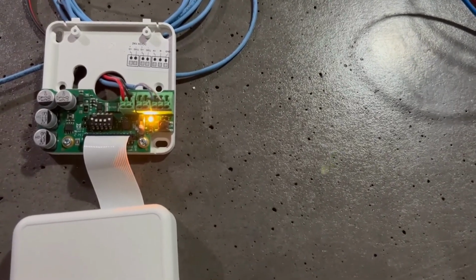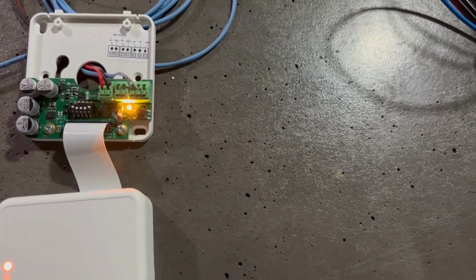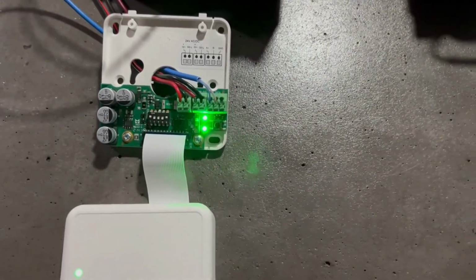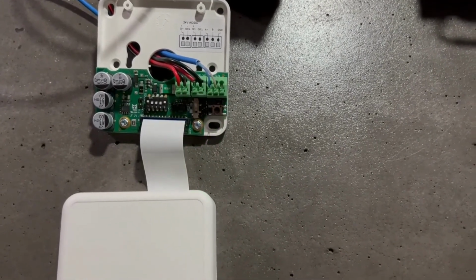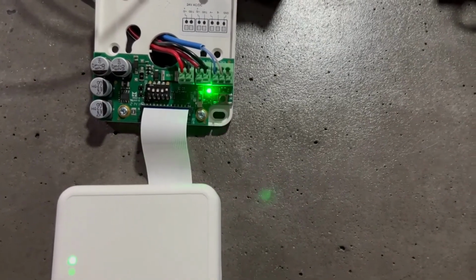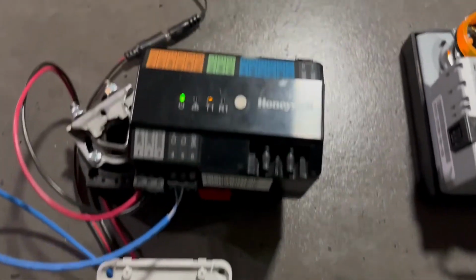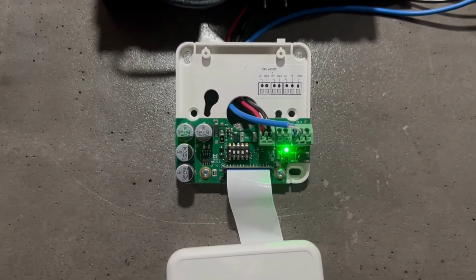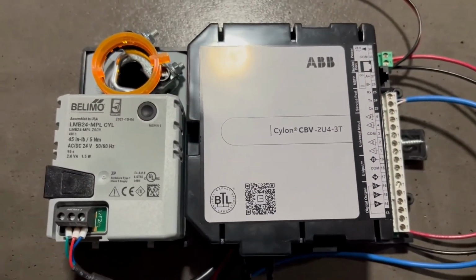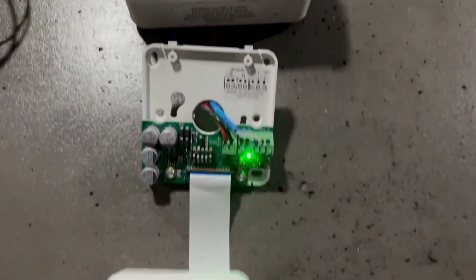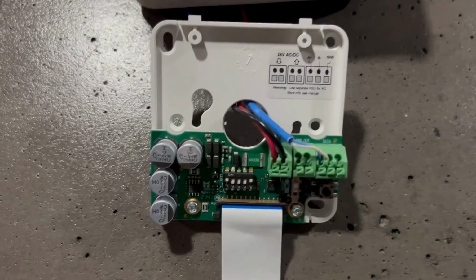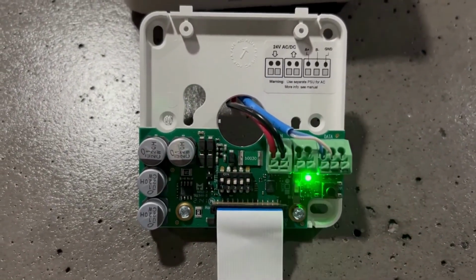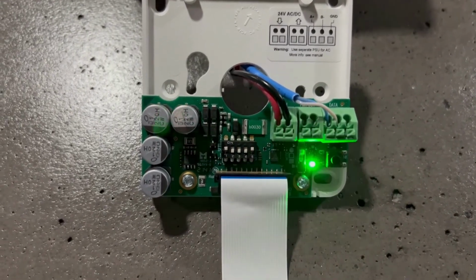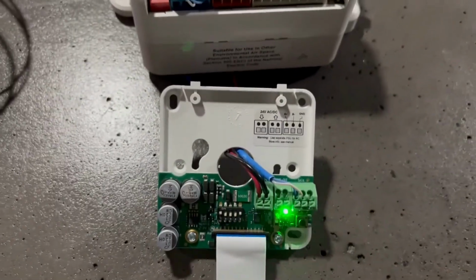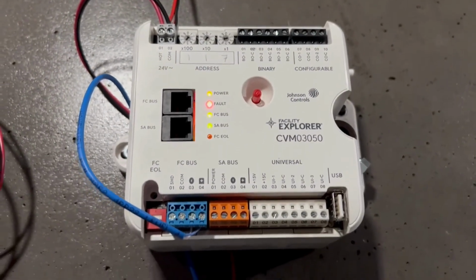So right now the gateway went to the top LED amber, signifying it is the gateway and it is set and running. And then we start seeing the top LED blinking green, that it's still finalizing its setup. The bottom LED blinking green means we have communications with the BACnet MSTP device. We move to the next one. We'll see the bottom LED blinking green, meaning it's connected and talking to the BACnet MSTP device. And if we move to the third node, you'll see the top LED is blinking green, signifying it's a node and it's still setting itself up. And then you have the green bottom LED that it is communicating with the MSTP controller.